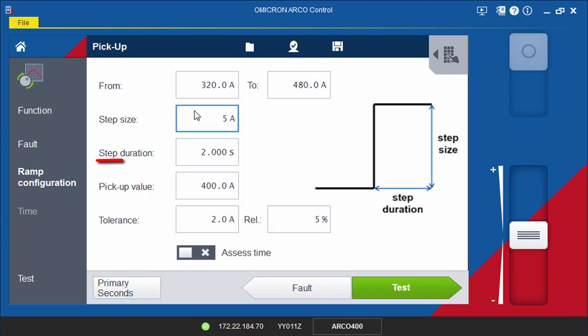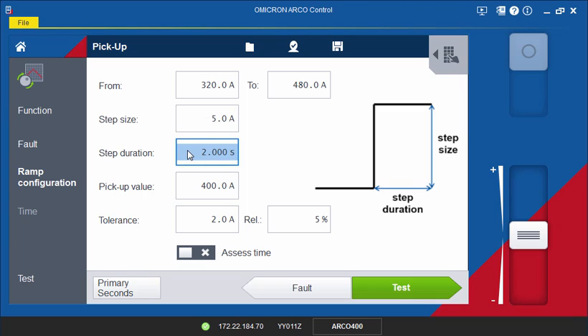The step duration is the period between two ramp steps. This duration must be set longer than the operating time of the controller. It should also be long enough for you to click the Manual Pickup button as soon as the controller picks up. We have set this time to 5 seconds.